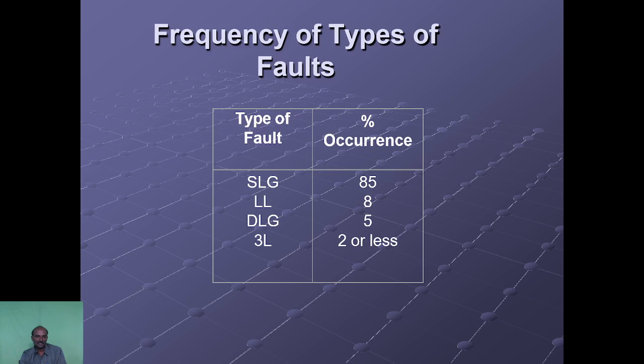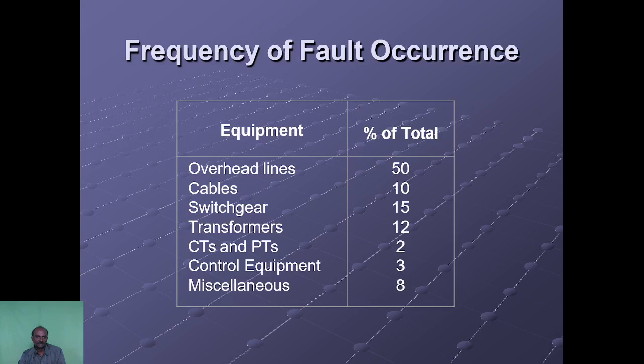Line to line fault is about 8%. Double line to ground fault is about 5%. Then three lines, it is about 2%. So the major possibility of occurrence of fault is the single line to ground fault. It is about 85%.